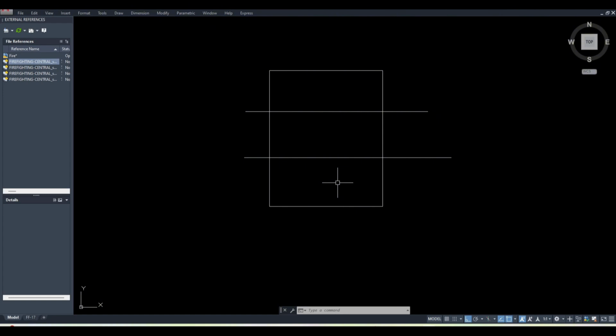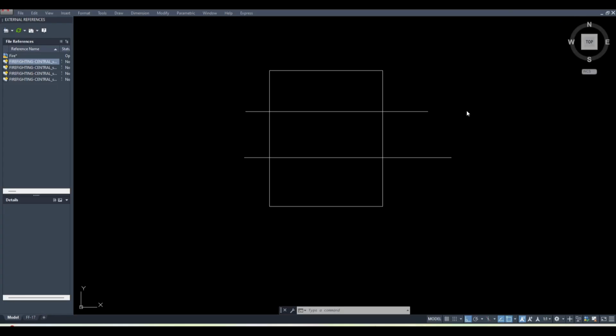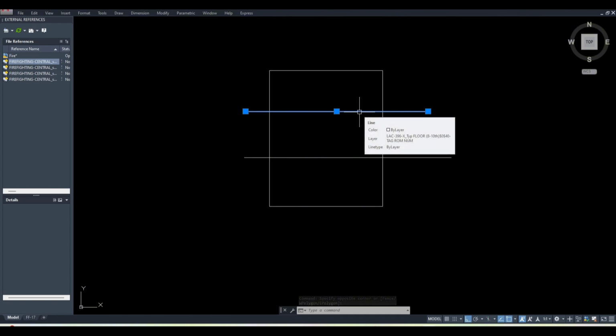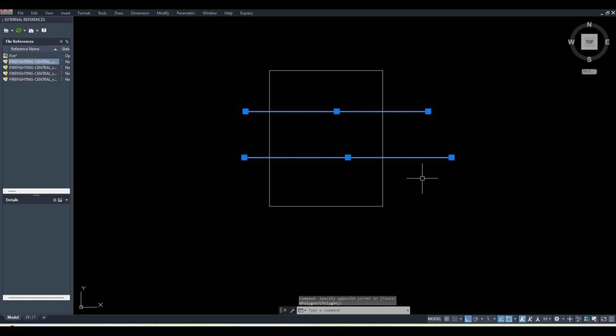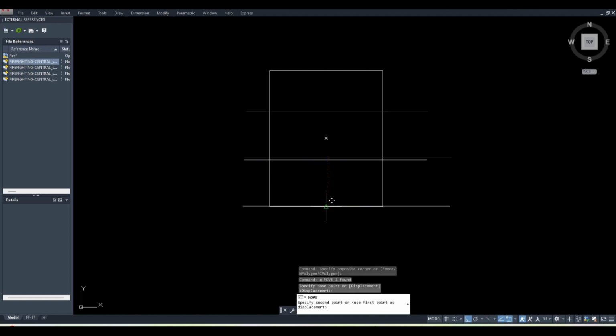Tell me, who can answer it quickly? No one? Anish, can you please ask once. The top floor has an area of 4,500 square meter. The floor below it has an area of 5,600 square meter, and the floor below it also has 5,600 square meter. So how many fire zones should come in this building for a sprinkler system?